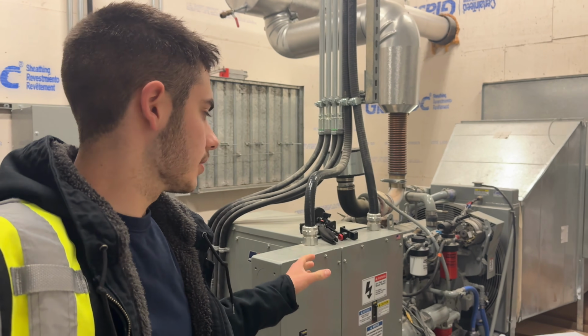Today we're going to be doing a real power outage generator test at this high school. This school has this 600 volt, I believe it's a 60 kW emergency generator. We'll check the nameplate on that, and we're going to be simulating a real power outage and seeing exactly how long it takes and just what happens.